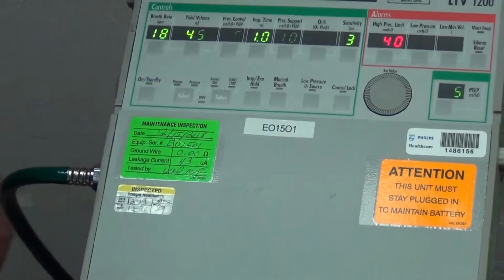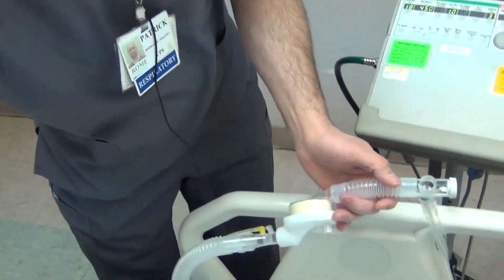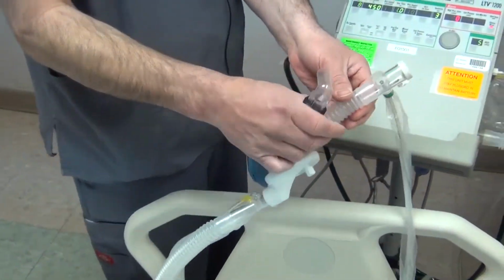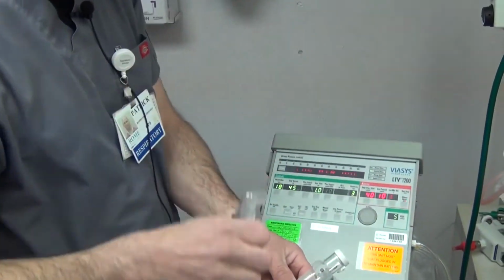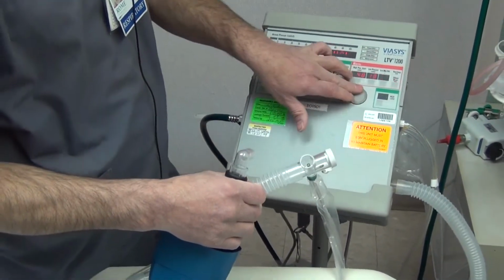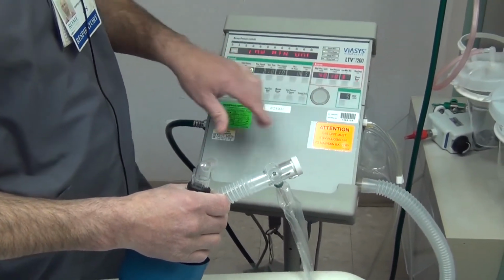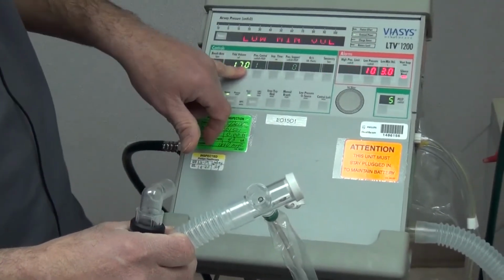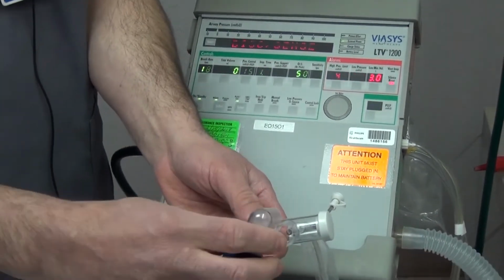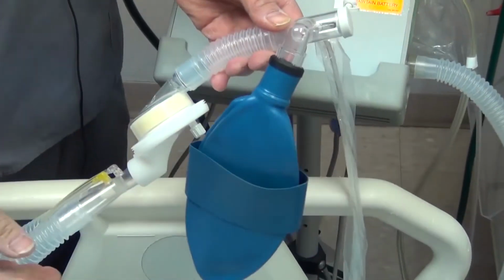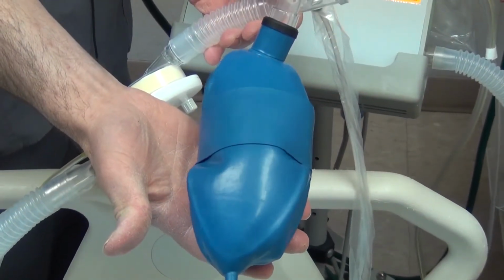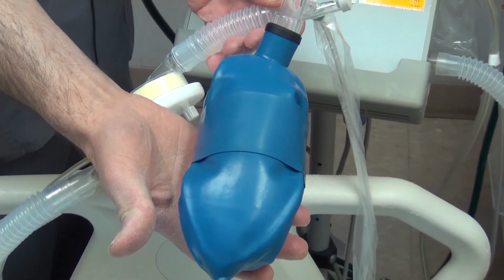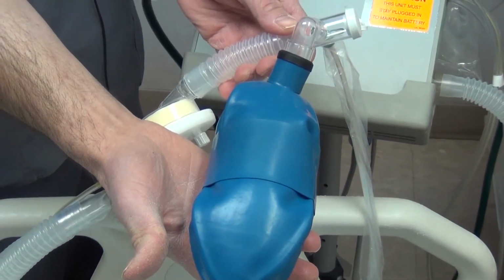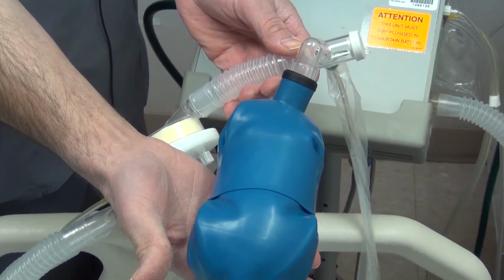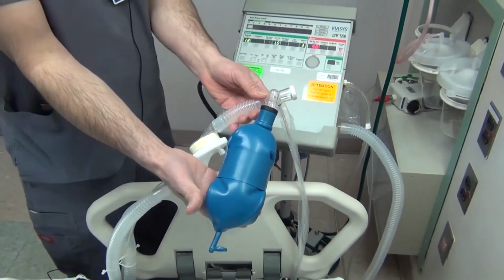At this point, we have our alarm set, we have our settings put in. We would just connect the patient. So again, because of our tidal volume of our test lung, we are going to decrease the tidal volume because it's not the normal size of a patient. And notice I dropped it to 170. You would connect the patient and then ventilation would start. And then the patient would be ventilating. And you can see the test lung opening and closing as the breaths are given.